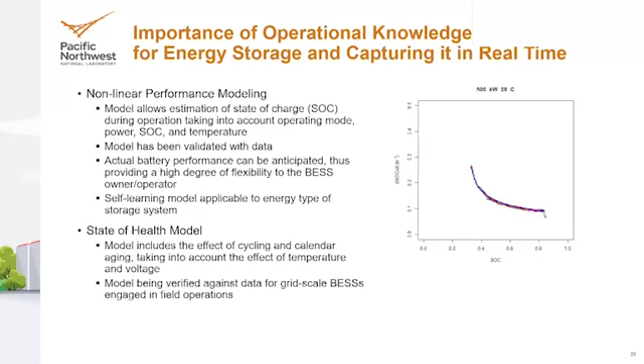With that, we learned we can generate much more value for the grid. If you have an economic assessment with perfect foresight and perfect information generating estimates of $1 million or $2 million per year in the real-time market, you know you're probably vastly overstating the benefits. So rather than estimating an ROI of 2.1 and then generating a real-time return on investment ratio of 0.6, we're hoping to generate ROI ratios of 1.1 and actually capture that 1.1 in real time. So we're aiding the development of control systems and improving the assessment of the actual expected performance of battery systems.